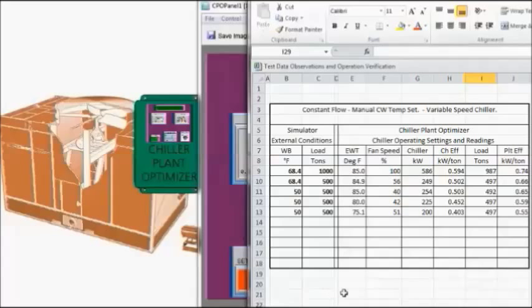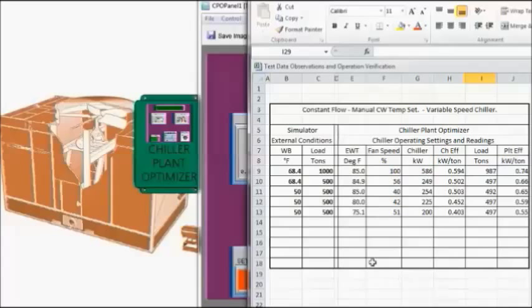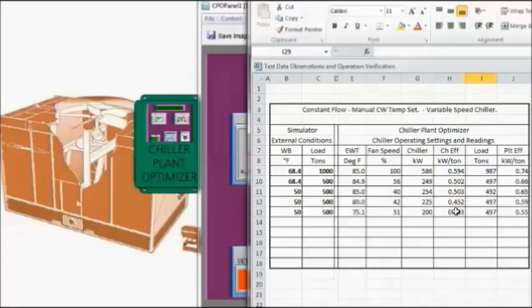So here I input this data. And as you can see, when we drop the entering condenser water temperature, we increase the fan speed, increasing its power usage. But we improve the chiller efficiency by quite a bit, resulting in an overall plant efficiency improvement.